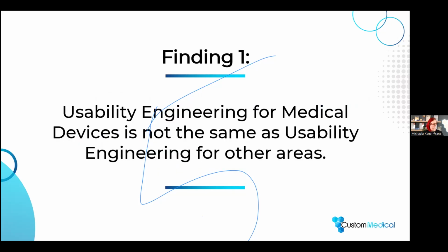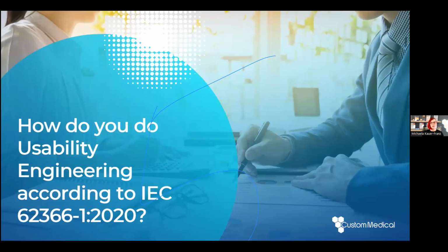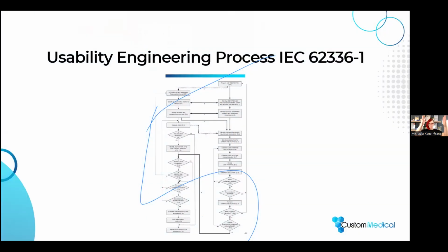Usability engineering for medical devices is not the same as usability engineering for every other area that you're working in, and it's all about safety. Therefore, let's have a look at the question of how you do usability engineering according to the standard. So this is the picture that you will see in the standard if you have it or if you know it. And as you can see, this picture is huge. So there is a huge amount of different steps that you have to consider to do usability engineering.